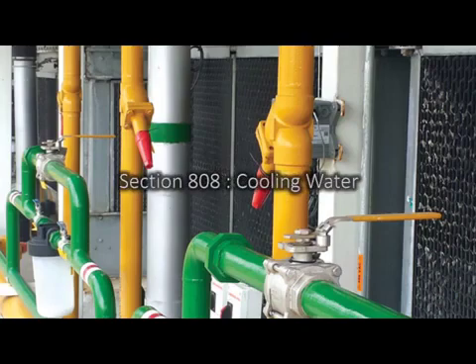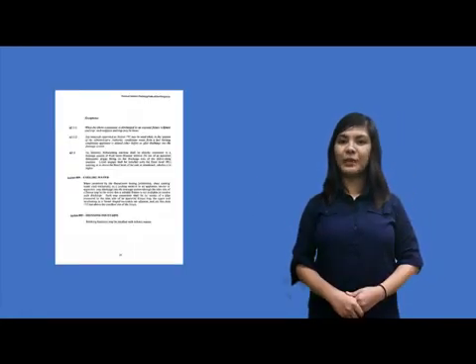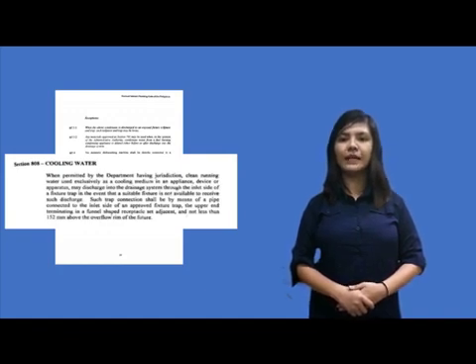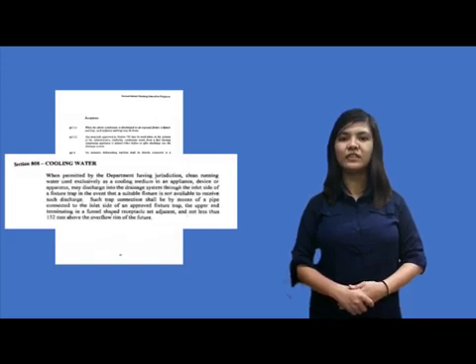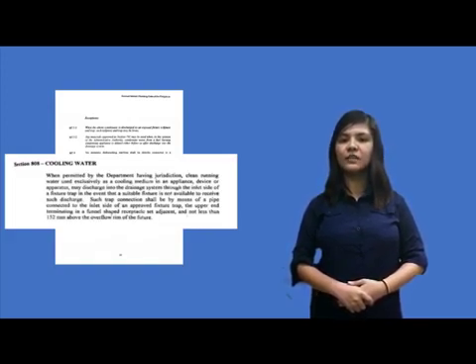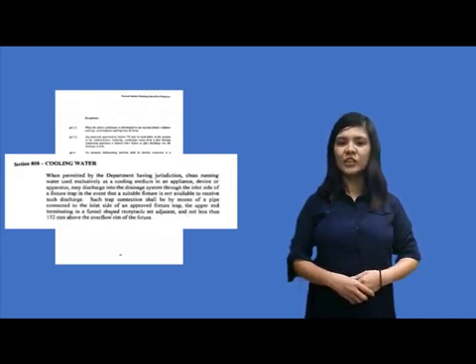Proceeding to Section 808, Cooling Water. Reading from the Revised National Plumbing Code of the Philippines, page 93: when permitted by the department having jurisdiction, clean running water used exclusively as a cooling medium in an appliance, device, or apparatus may discharge into the drainage system through the inlet side of a fixture trap in the event that a suitable fixture is not available to receive such discharge. Such a trap connection shall be by means of a pipe connected to the inlet side of an approved fixture trap, with the upper end terminating in a funnel shape set adjacent and not less than 152 mm above the overflowing rim of the fixture. It means you can discharge waste temporarily to the inlet side of a fixture as an alternative when no suitable fixture is available.